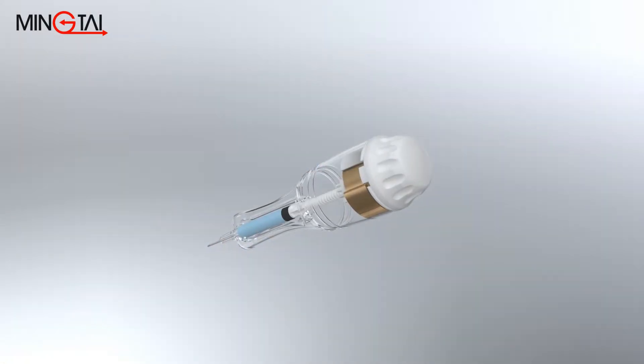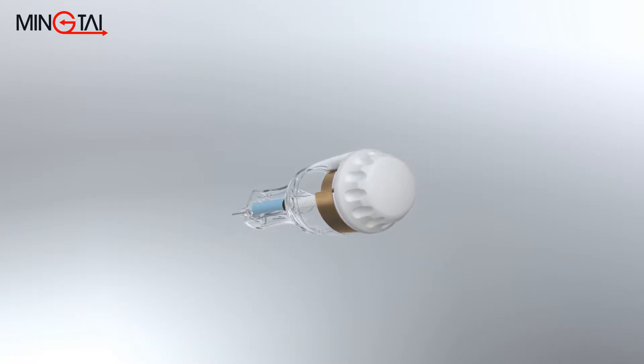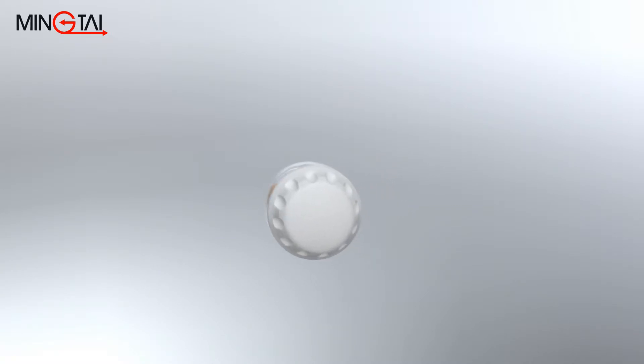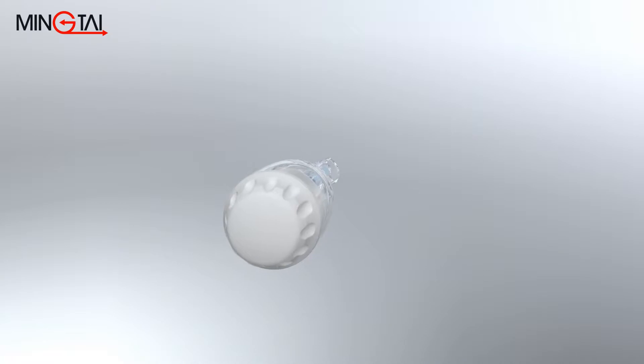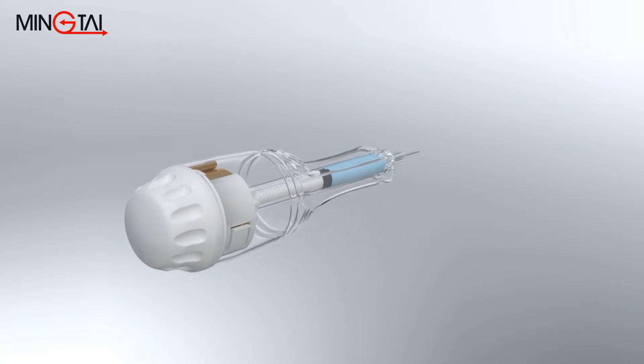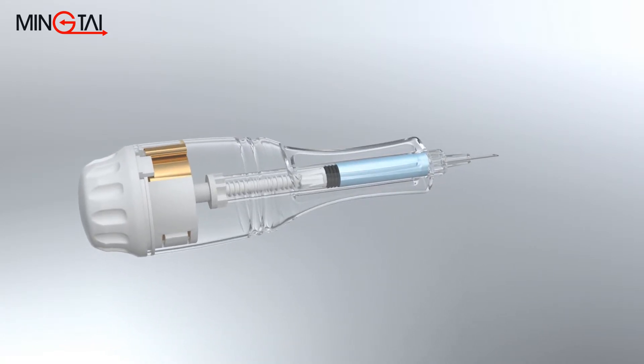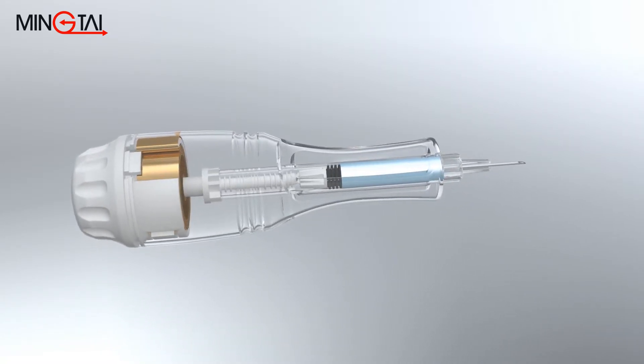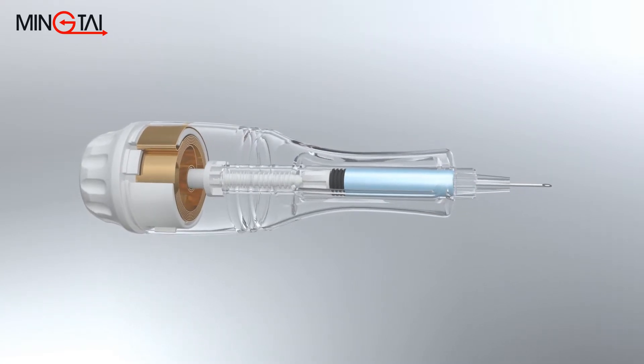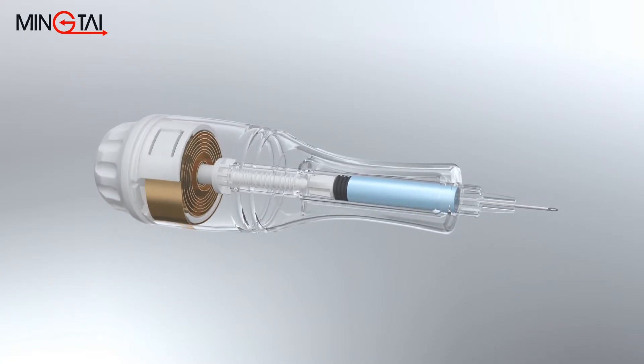The new Precision Pen-type injector uses a pre-stressed power spring to deliver small but highly accurate doses of medication. Power springs are pre-stressed to produce a torque, which provides rotational energy from either the arbor or the case, or linear motion with the use of a screw. Through the torque of the power spring, the total rotational energy gives the screw a linear motion to push the drug ahead and to inject it into the body at a fixed speed and quantity.